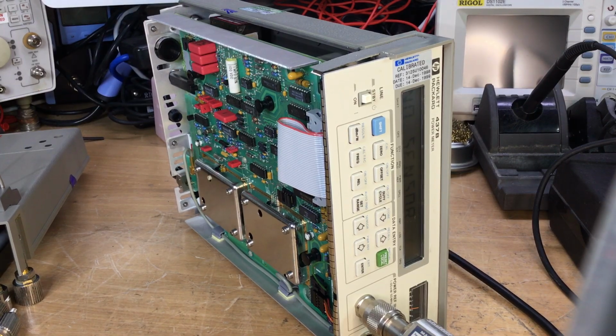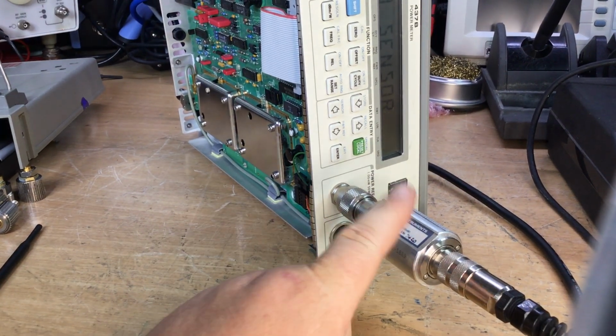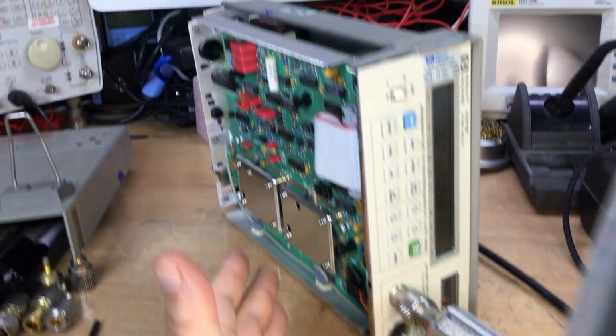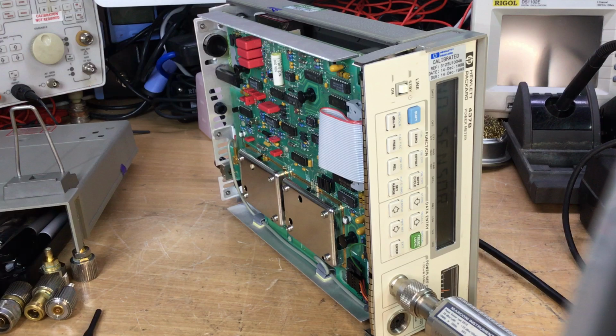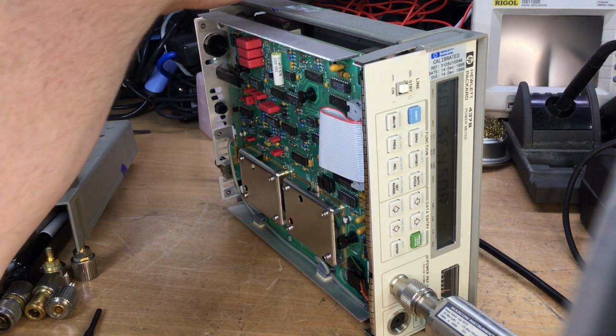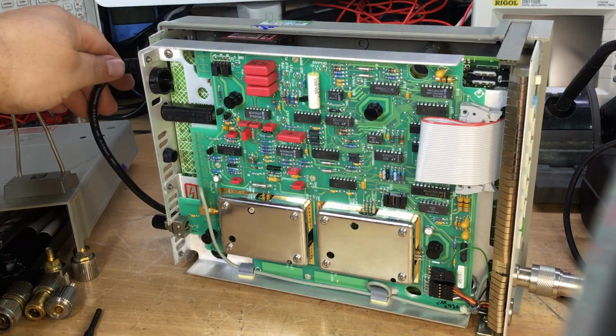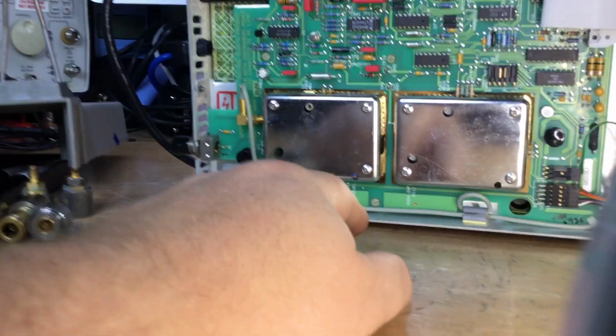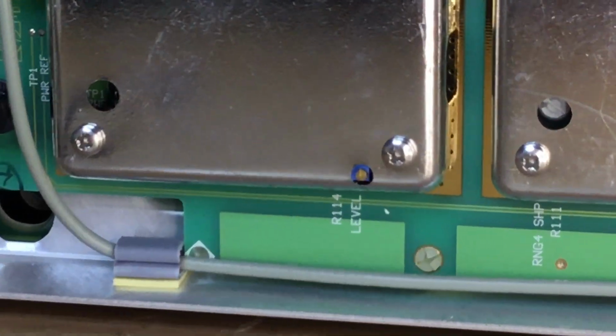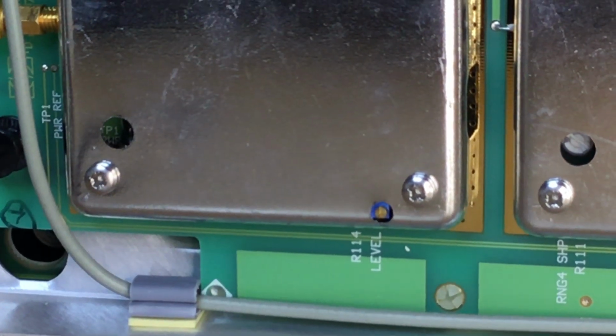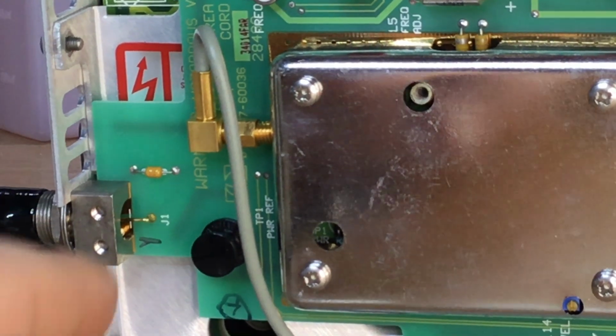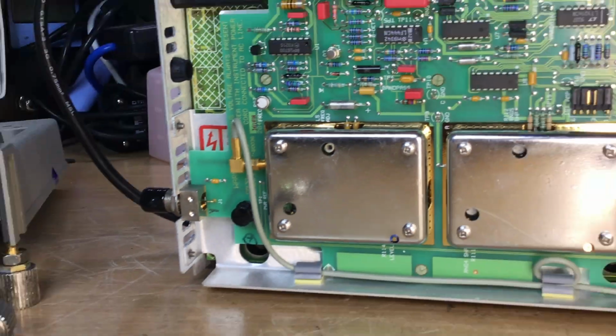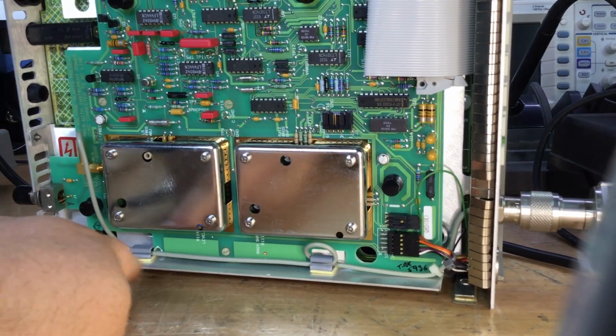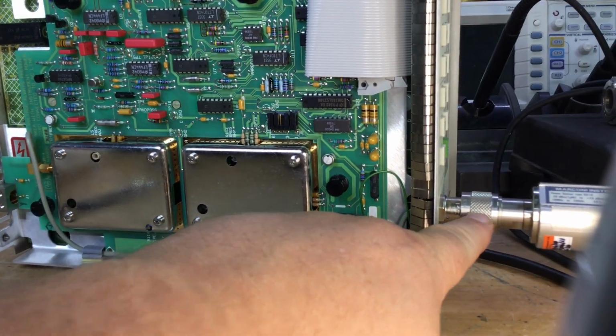Right, so we've got the Marconi sensor plugged in on this meter. We whip the lid off so we can calibrate it against the Marconi calibrated test instrument. Now just under here there's a potentiometer, and if I zoom in you might be able to see it, it says reference level there. So we've obviously got the RF output here coming away, and that makes its way down the side here to the front connector there.